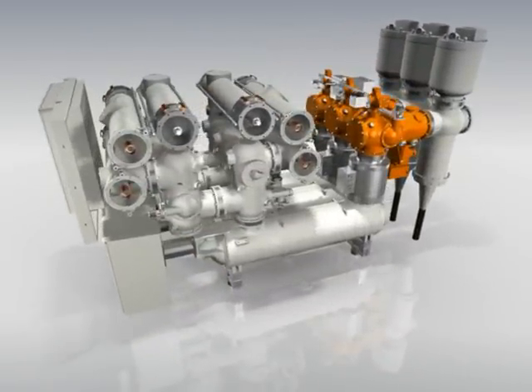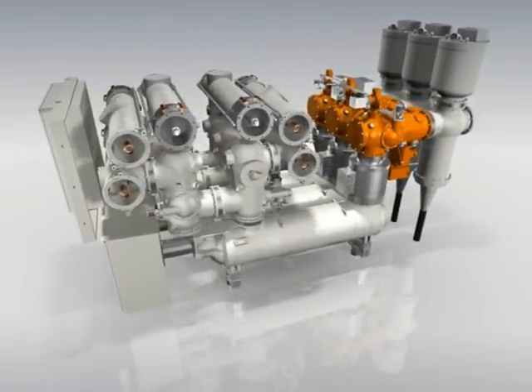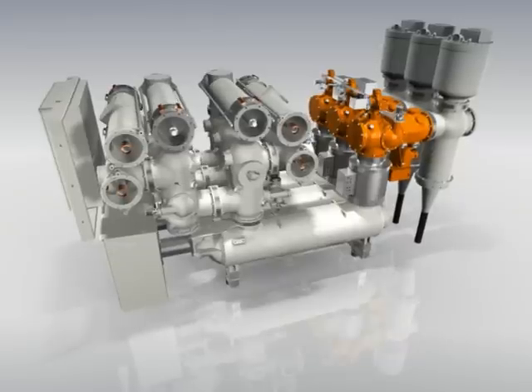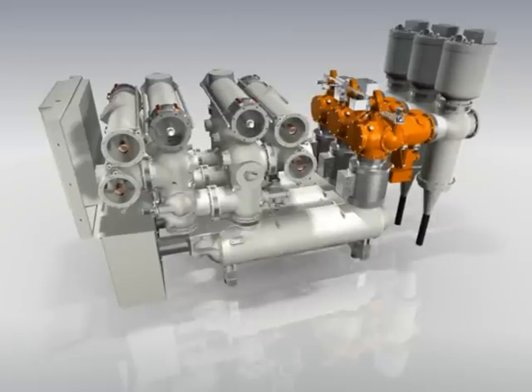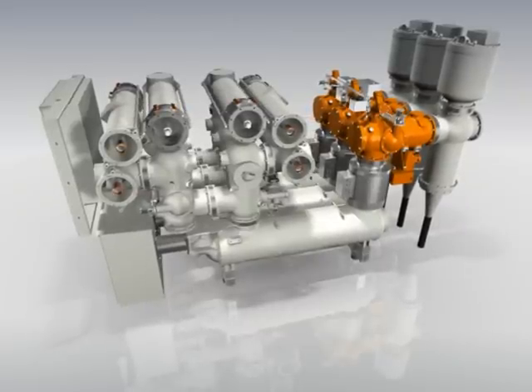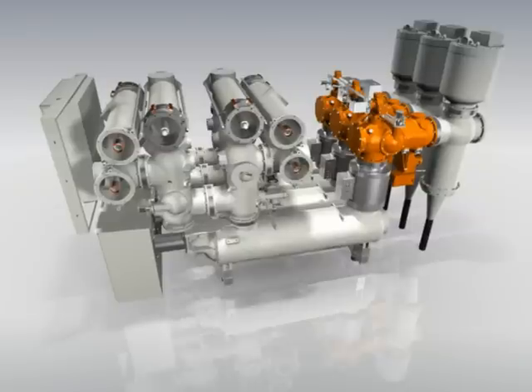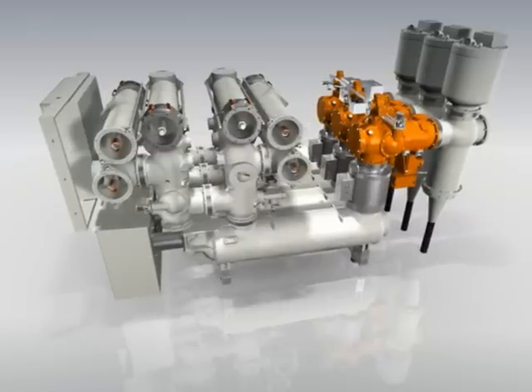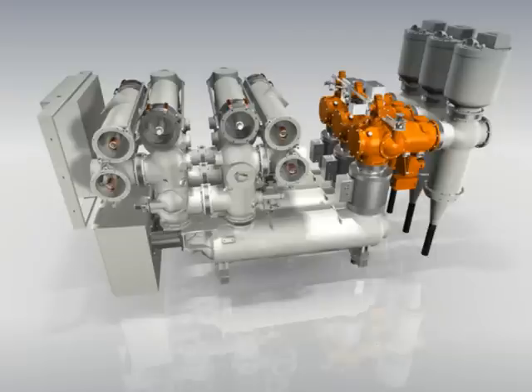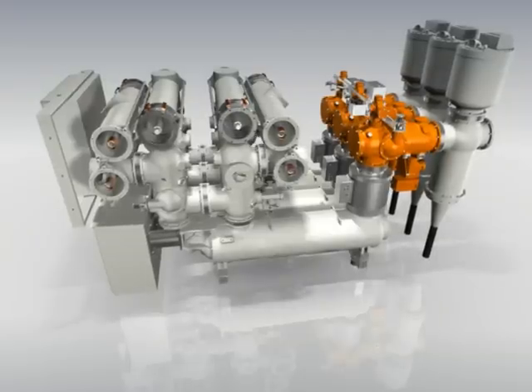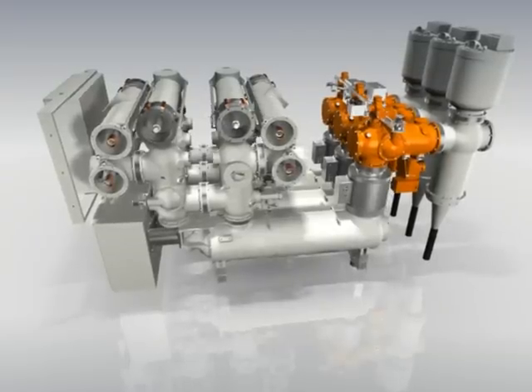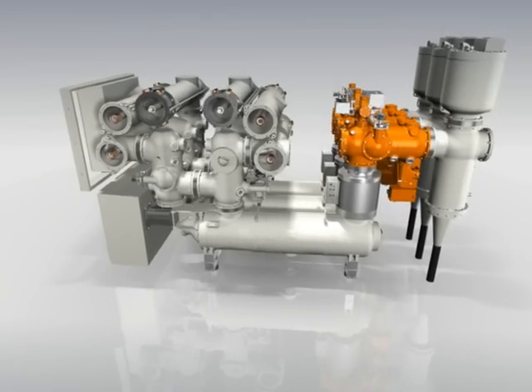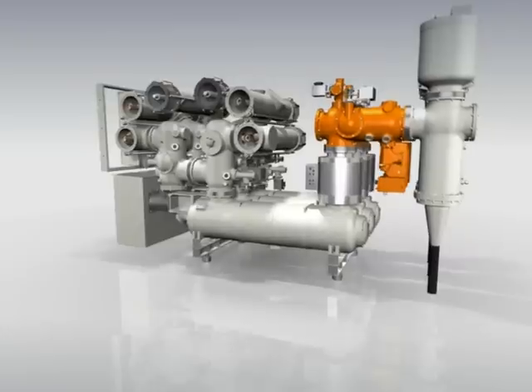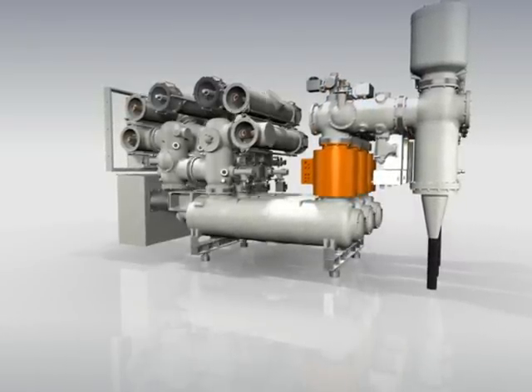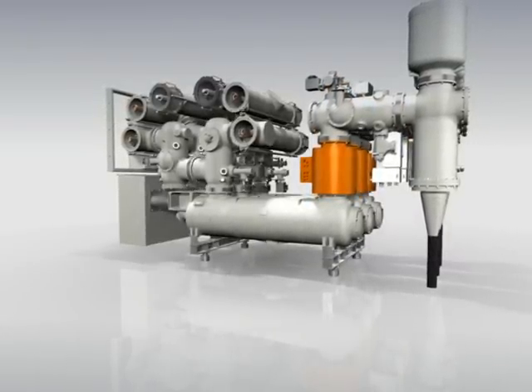Disconnecting and earthing are integrated in one multifunctional module, which is used for busbar switching as well as for cable, overhead line, and transformer termination. Earthing and short-circuiting of system components like overhead lines, cables, and transformers after isolation can be performed through either a work-in-progress switch or a high-speed earthing switch. Thanks to large viewports, the position of either the disconnector or the earthing switch is easily visible in any case. The current transformer, available as either inside or outside SF6 core inductive transformer, serves various measuring and protection purposes.